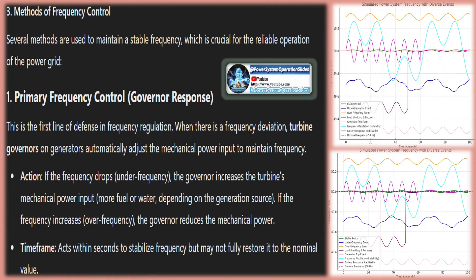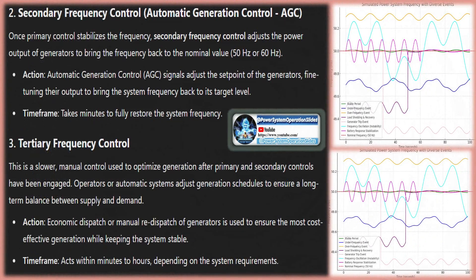Changes in supply and demand impact frequency — excess demand drops the frequency, while excess supply raises it. We are required to keep the frequency within 0.5 Hertz of 50 Hertz, but we aim for a tighter operational target of 0.2 Hertz. The trend in system frequency is a measure of mismatch between demand and generation, and so is a necessary parameter for load control in interconnected systems.